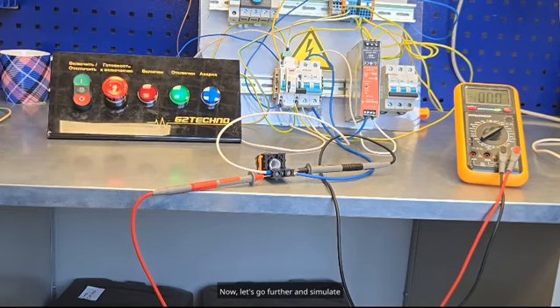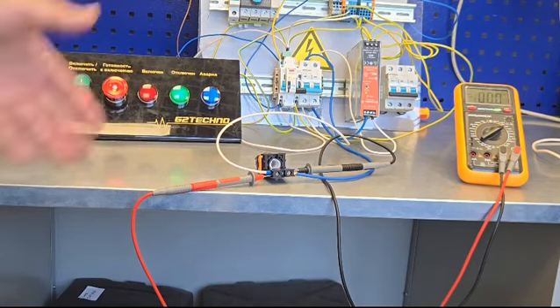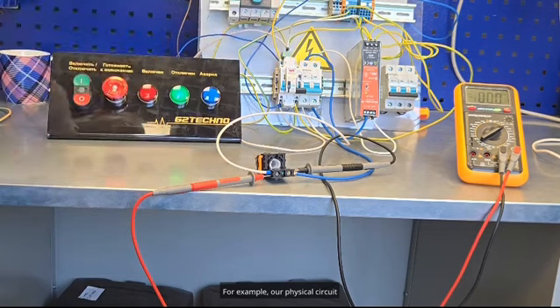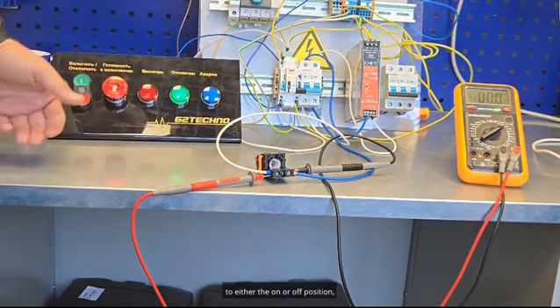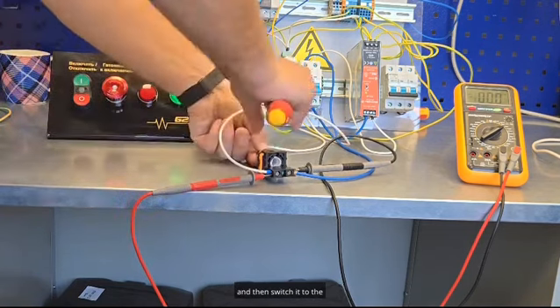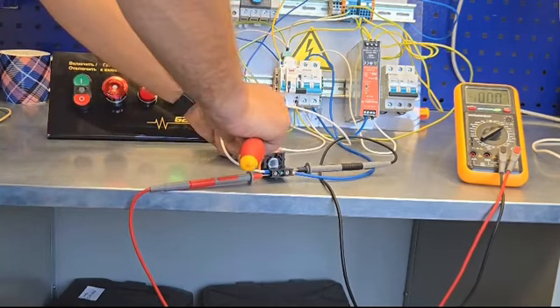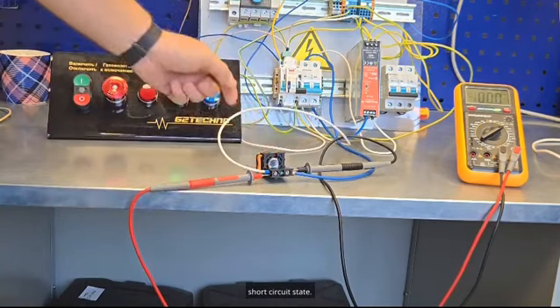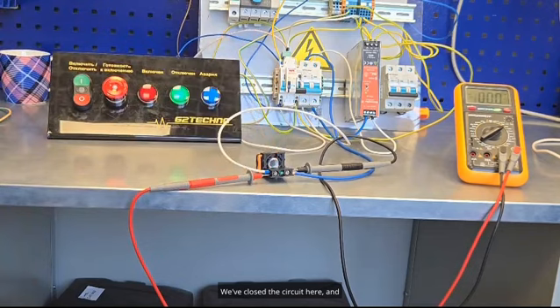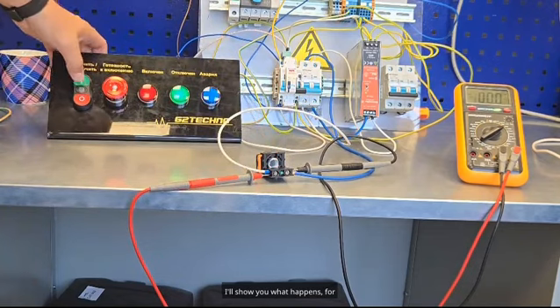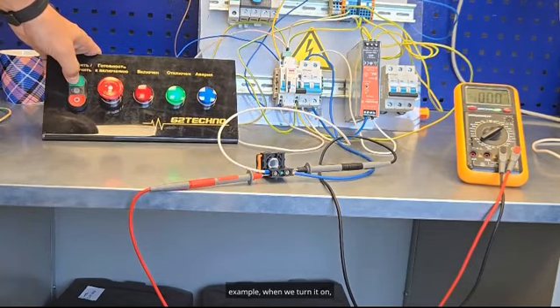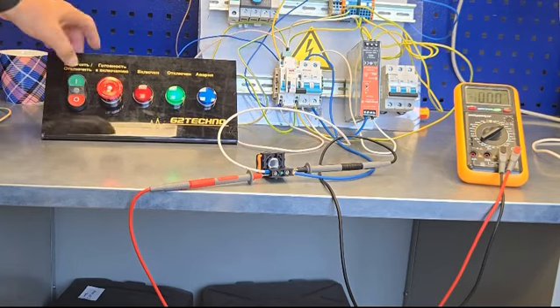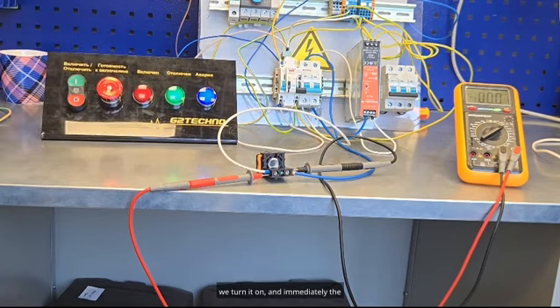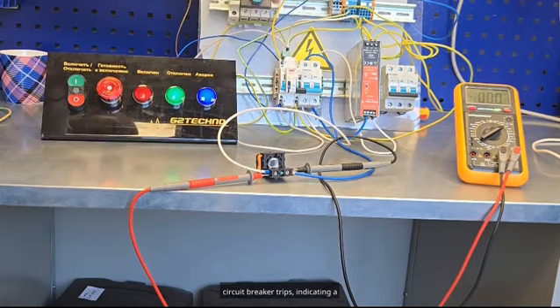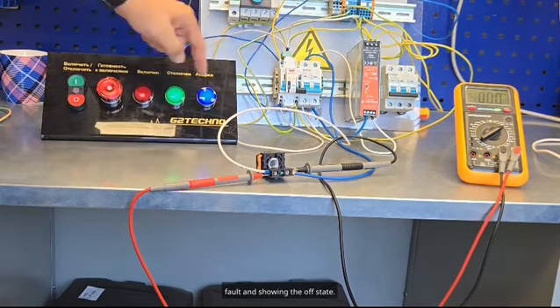Now let's go further and simulate a short circuit. For example, our physical circuit breaker is off, but we can set it to either the on or off position and then switch it to the short circuit state. We've closed the circuit here, and that's enough for our purposes. I'll show you what happens, for example, when we turn it on. We turn it on, and immediately the circuit breaker trips, indicating a fault and showing the off state.